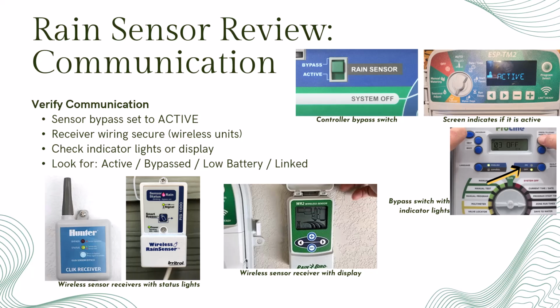For wireless sensors, I inspect the receiver and look for communication lights or display icons. They should show that the sensor is connected and active. Some models will also show battery levels, bypass indicators, or signal strength. If I see any alerts or warnings, I document them on the service checklist before testing.